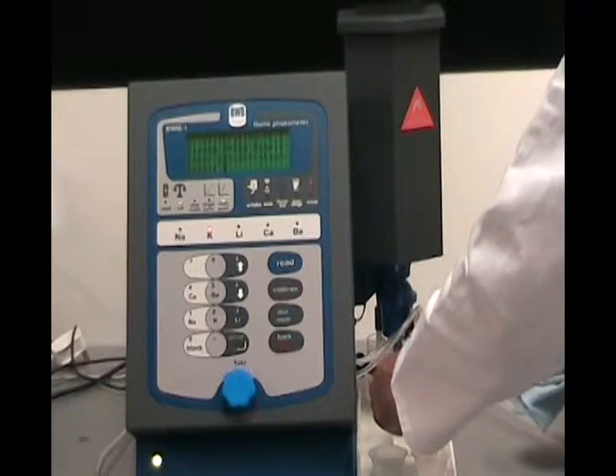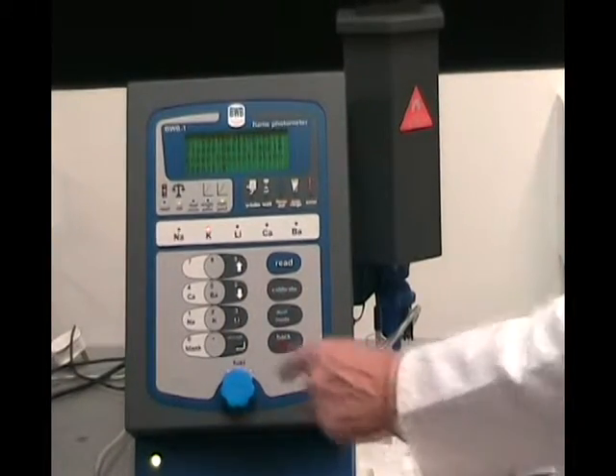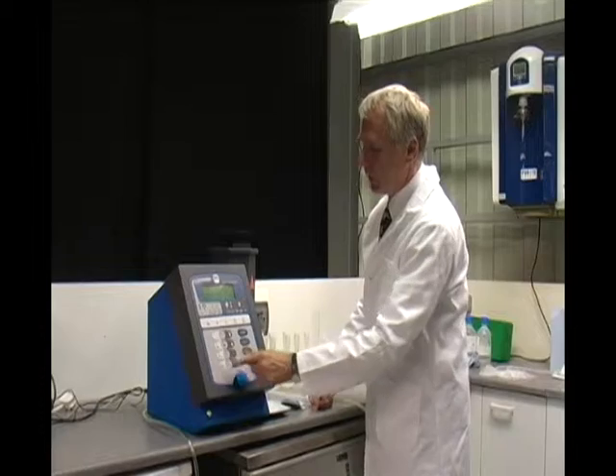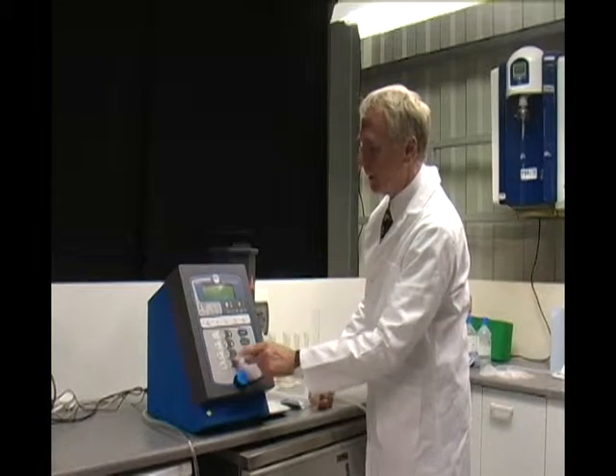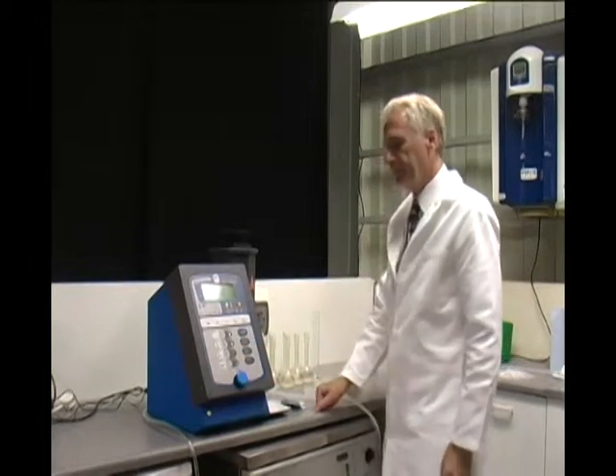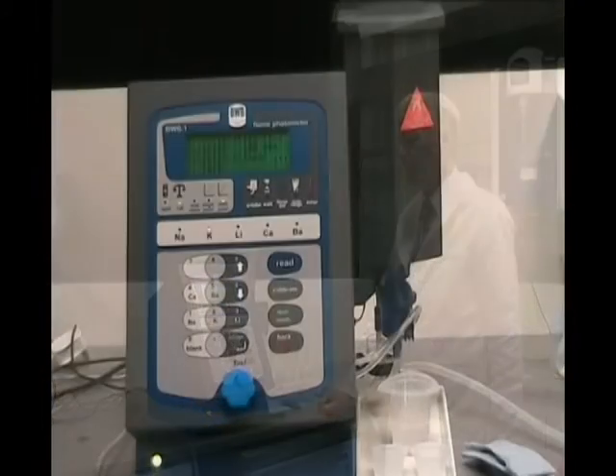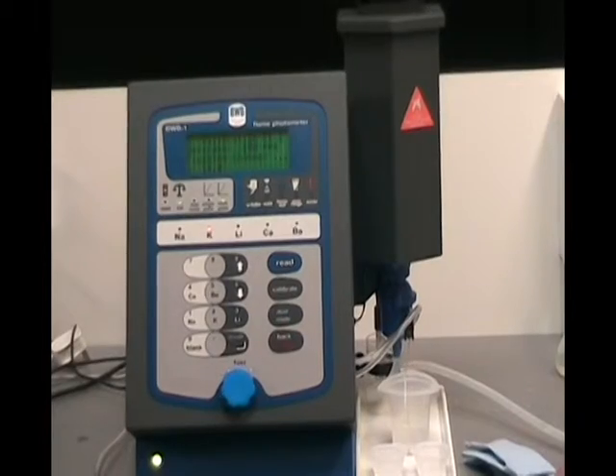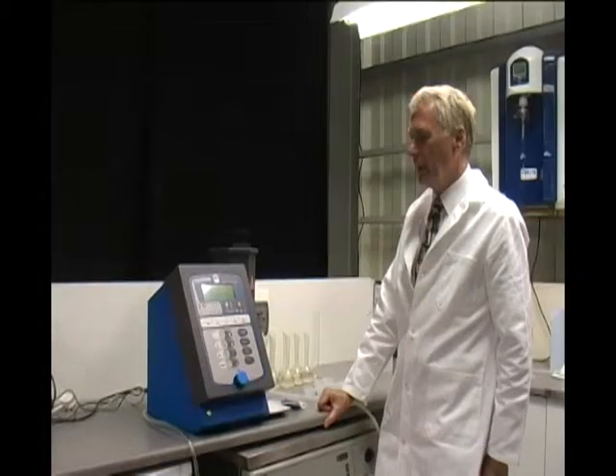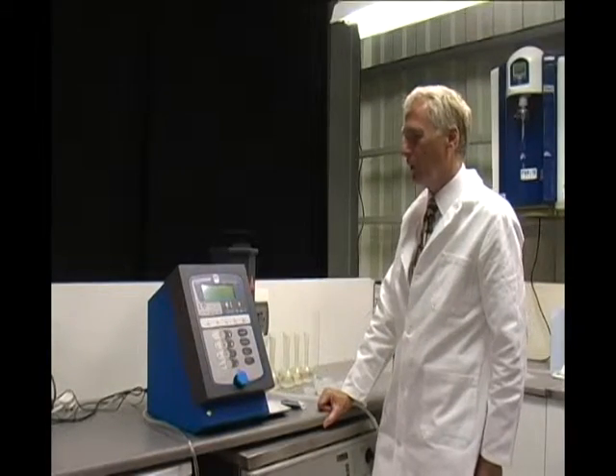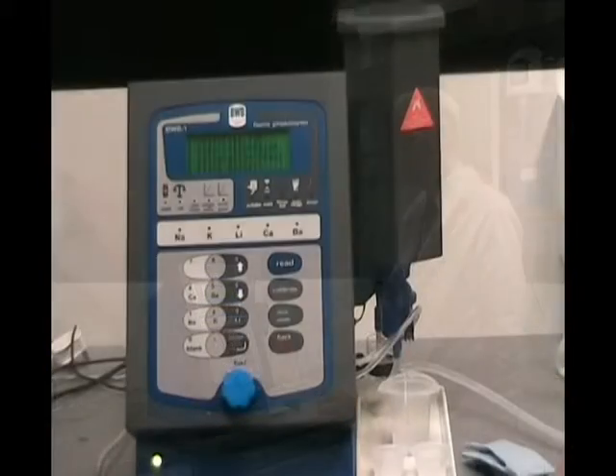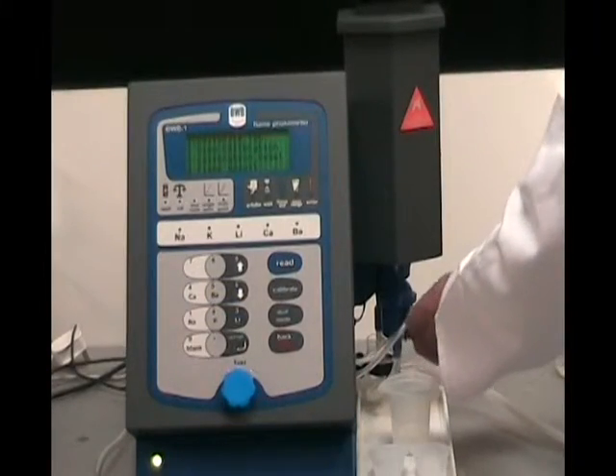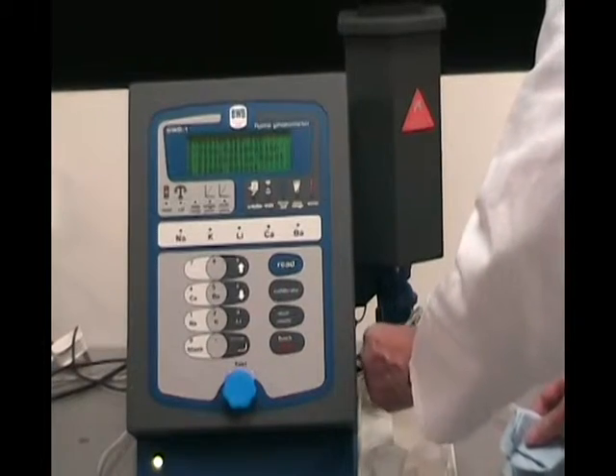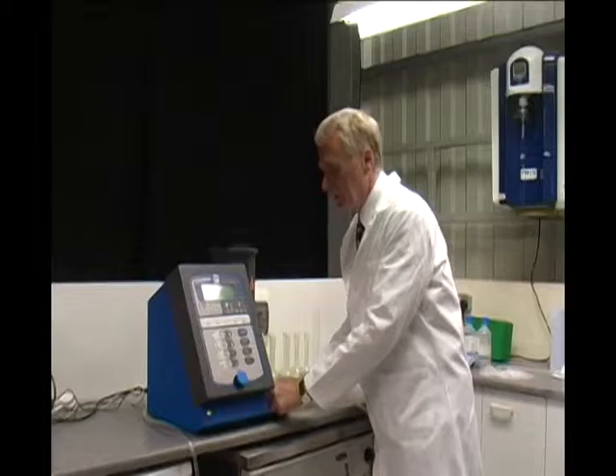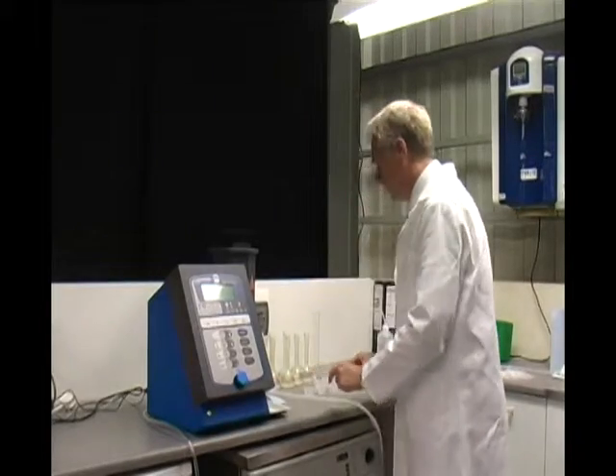I can move my aspiration tube into my 100 ppm sample, tell the machine that it's at 100 ppm and begin the process again. Once again a nice flat line and a single dot, meaning that we haven't got any noise in the system. It is now taking the reading that it requires for the 100 ppm solution. Finally, clean the aspiration tube and put it back into the deionized water so that it will flush the chamber completely before we do another calibration.